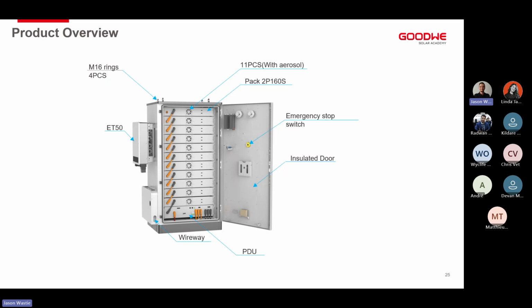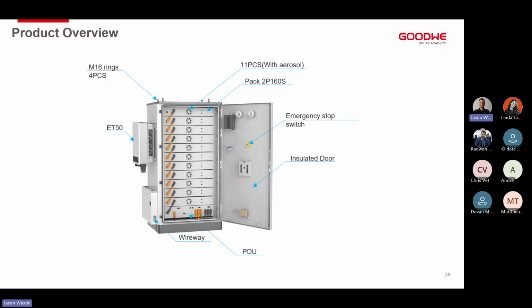However, this is what the battery rack would look like. It comes pre-built from the factory. The only thing you need to wire in are your DC cables going from the battery to your inverter, and the AC cabling from your smoke detectors and emergency stop into the system itself. The back end of this cabinet has an air conditioning unit with which we can regulate the temperature. On the top, there are M16 rings to be able to carry it in by crane. At the bottom, next to the wireways, we have two different forklift options: either the standard forklift, or, if you're coming in from the side, a narrow-armed forklift. But please do note that this battery comes already pre-installed as you see it here. Only the DC and AC cables need to be connected on the actual PDU, or power distribution unit, at the bottom.